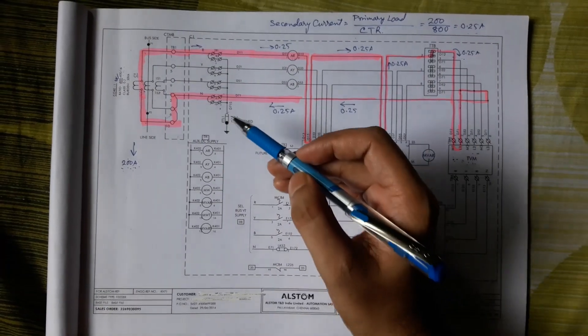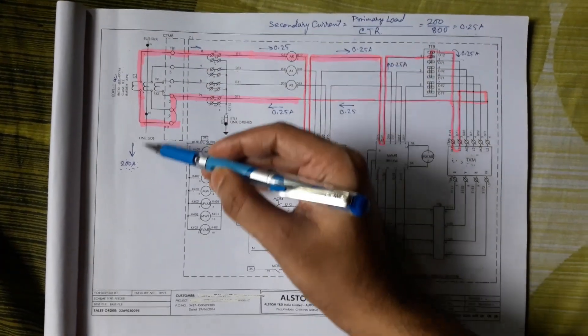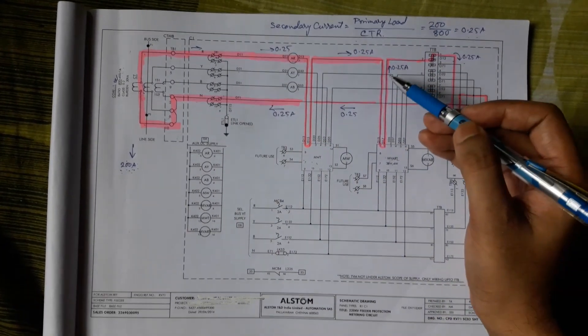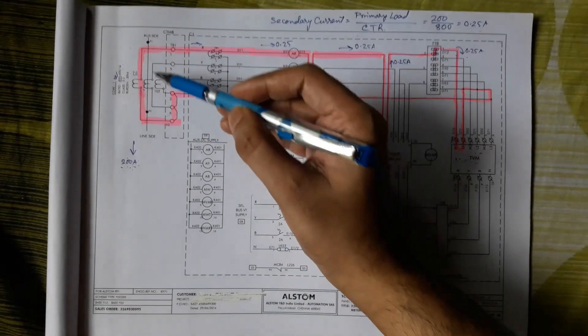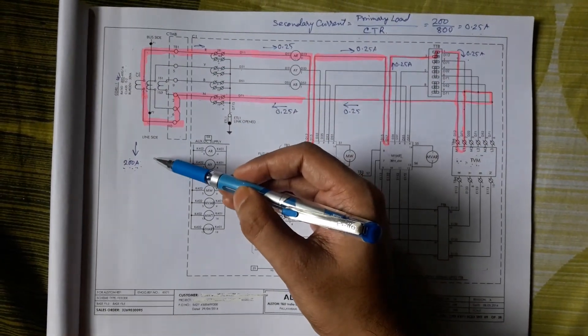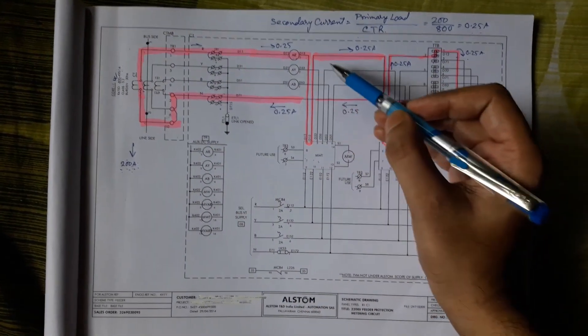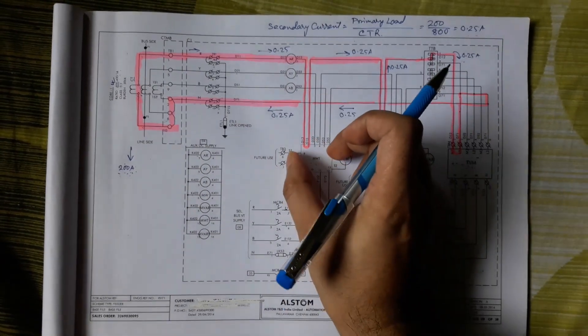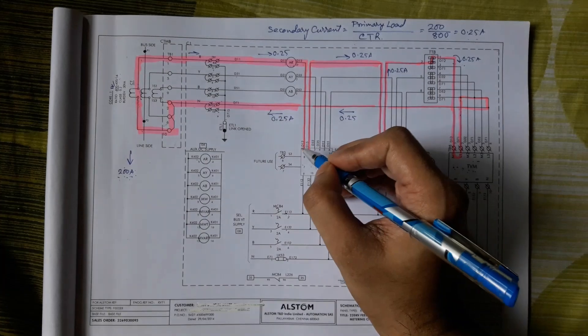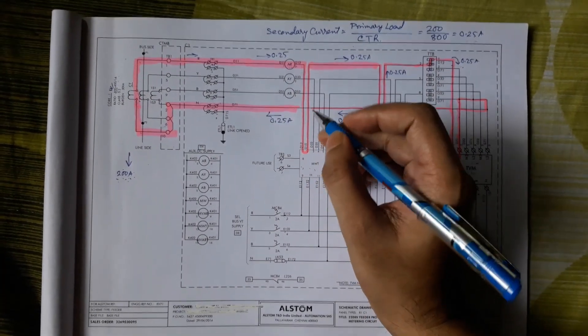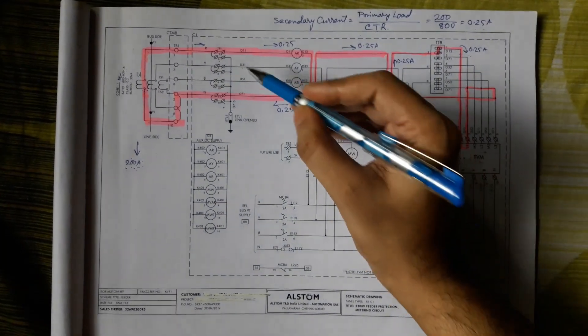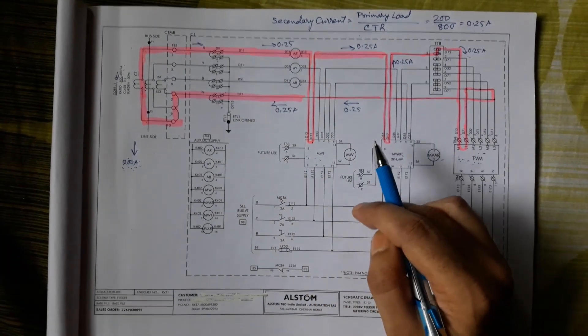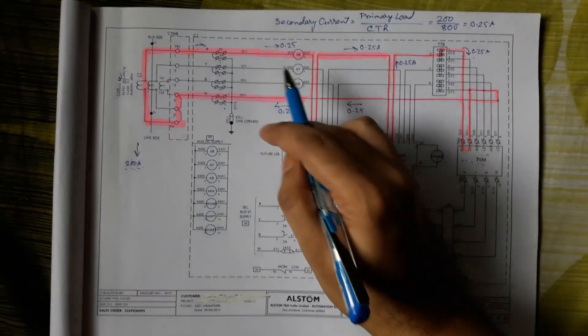There may be a situation where current flows through the primary circuit of the CT but we want to take all panel equipment out of circuit for maintenance. We cannot simply disconnect the equipment because that would open the CT secondary path, which must never happen. But if we have a CT shorting arrangement, we can safely take out one or more equipment from the CT secondary circuit.